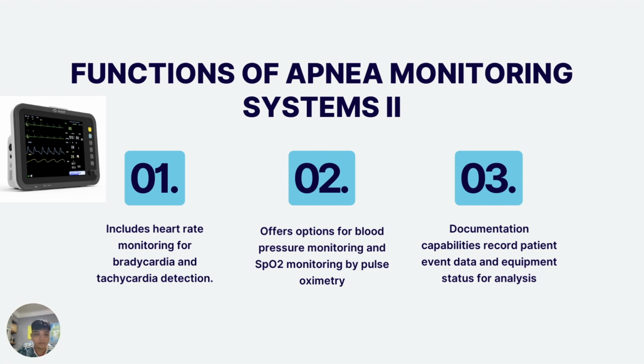monitoring process. Additionally, the monitors are equipped with documentation capabilities, allowing them to record patients' event data, including their respiratory and heart rates, as well as equipment data, giving us the power status and battery levels. This recorded data serves various purposes, including verifying proper monitor usage, differentiating true alarms from false ones, and troubleshooting equipment issues.